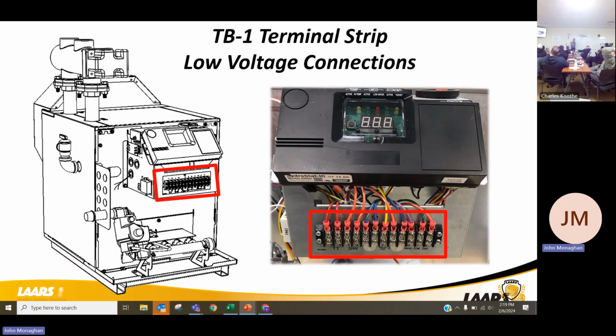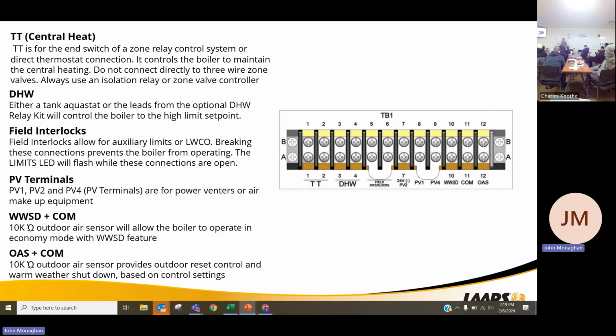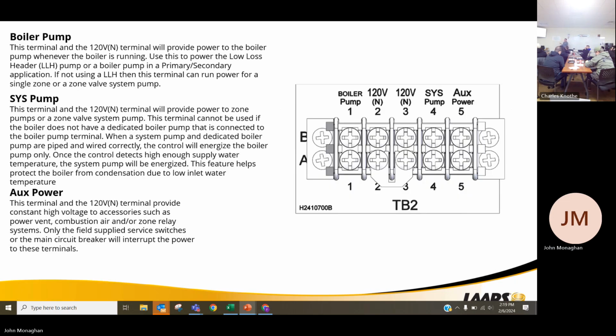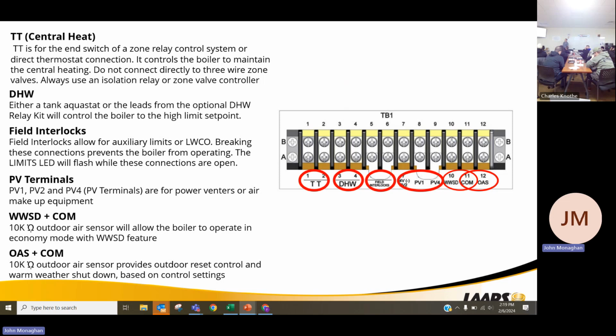Low voltage terminals on there. You're going to have your low voltage strip. That's going to be for your thermostat connections, your outdoor sensor if you're using one, and your domestic hot water landings. If you're using your power vent, PV1, PV4, your interlocks for your power vent are basically going to be for the pressure switches that are built into it. So TT, DHW, you can do an indirect tank to DHW, but we won't have the pump interrupt feature. That's when you would purchase the optional relay kit. Then we can do pump interrupt during domestic.